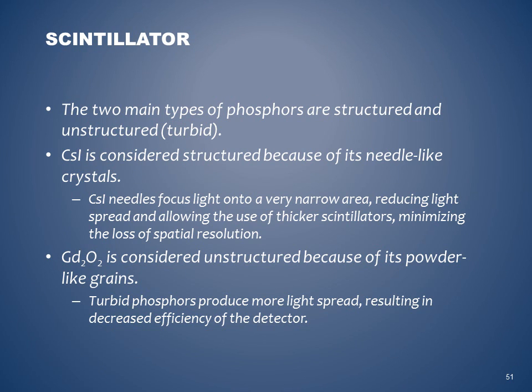Scintillator. The two main types of phosphors are structured and unstructured. So CsI is considered structured because of its needle-like crystals. Gd2O2S is considered unstructured because of its powder-like grains. So CsI needles focus light into a very narrow area, reduce light spread, and allow the use of thicker scintillators, minimizing the loss of spatial resolution. Turbid phosphors produce more light spread, resulting in decreased efficiency of the detector.